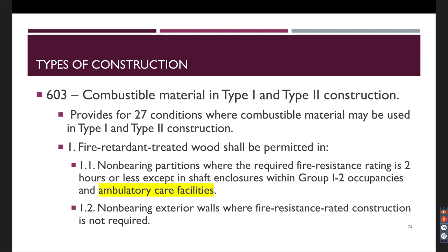So bringing it back around to type of construction and finishing it off, section 603 actually is one of my favorite sections because while we pointed out that type 1 and type 2 are considered non-combustible construction, 603 offers 27 different conditions where combustible materials can actually be used in type 1 and type 2 construction. So be familiar with this and the 27 items. And specifically for ambulatory care facilities, just wanted to point out that in item number 1, non-load bearing partitions where the rating is 2 hours or less can have combustible constructed walls, even in type 1 fire resistant buildings.